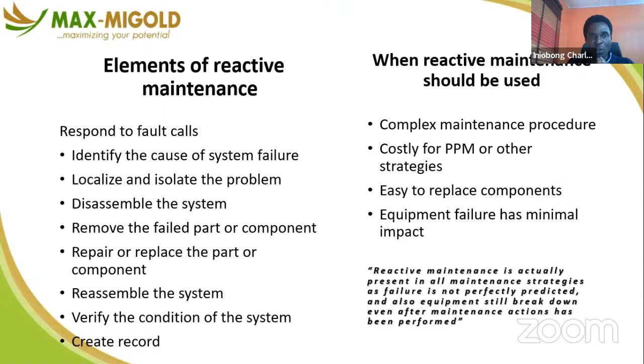Reactive maintenance is actually present in all maintenance strategies, as failure is not perfectly predicted, and equipment can still break down even after maintenance has been performed. Even if you're servicing your generator every month, at the end of the day you'll still have one reactive maintenance to do on it, because failure won't tell you when it's coming. But the good thing is other maintenance strategies can reduce that sudden failure, reducing the failure rate to a very low level.